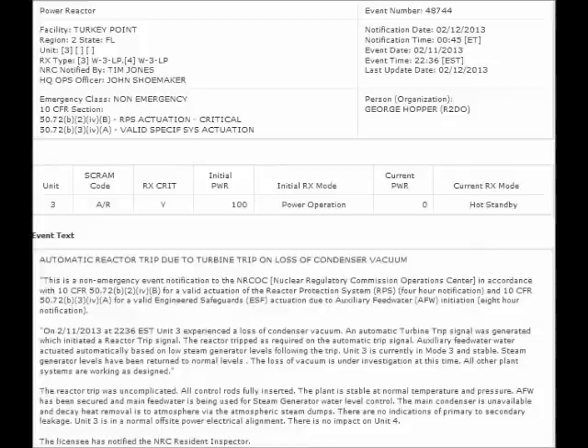NRC event notification report for February 12, 2013. On February 11, 2013, Unit 3 experienced a loss of condenser vacuum. An automatic turbine trip signal was generated, which initiated a reactor trip signal. The reactor tripped as required on the automatic trip signal. Auxiliary feedwater actuated automatically based on low steam generator levels following the trip. The loss of vacuum was under investigation at the time. All control rods were fully inserted. The main condenser was unavailable and decay heat removal was to atmosphere via the atmospheric steam dumps. There were no indications of primary to secondary leakage — otherwise, apparently, they would have been dumping radioactive steam into the atmosphere.